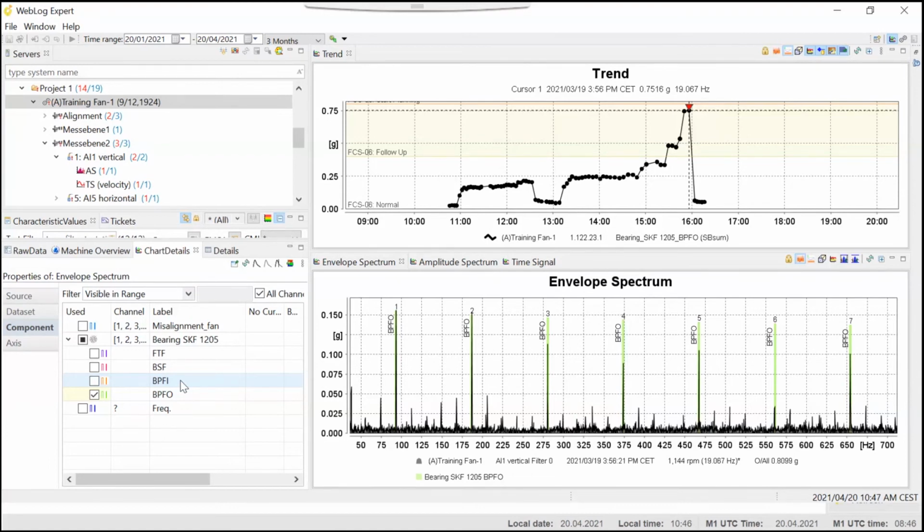So to analyze in detail what's wrong with a bearing or a gearbox or something else, you need to know the details of this bearing. If you go on the vessel, you can show the crew that there's something wrong, but because you don't know what kind of bearing is installed within that system on board, you need to add this information to your data to be able to analyze what exactly is wrong.